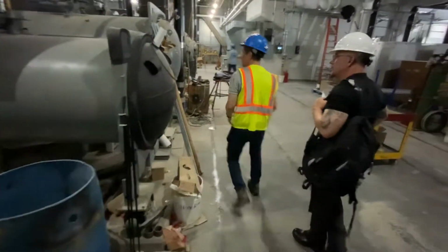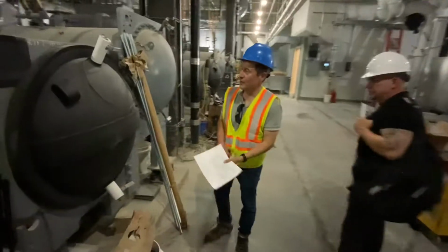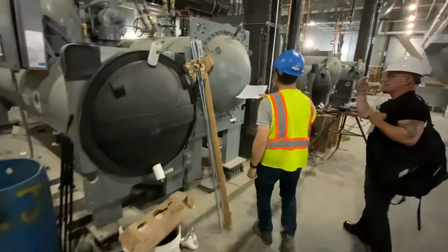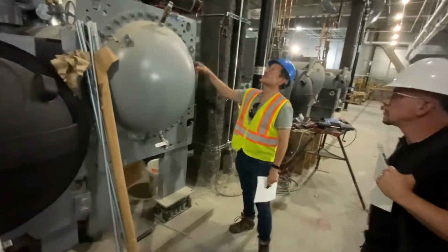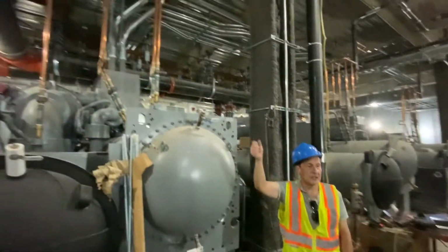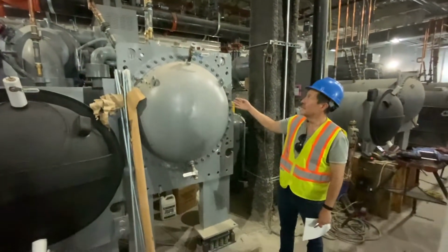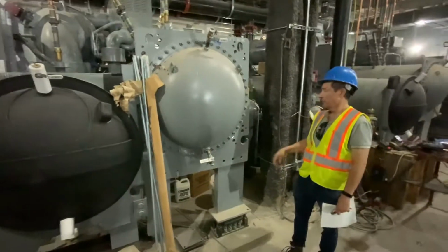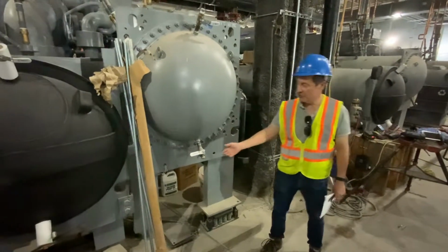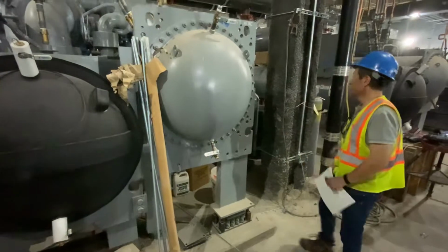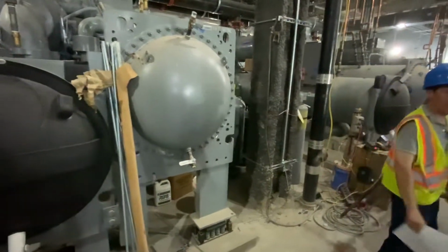Go over to the condenser water side. When we clean condensers, the condenser side's over here. Pretty much it is clean here. You're going to have to get some overhead pull chain or a gantry to pull these off, and then you'll take a toothbrush. You can drain it from here. Toothbrush, brush them all out. Clean really good. Let's go around to the back of some of the other chillers.